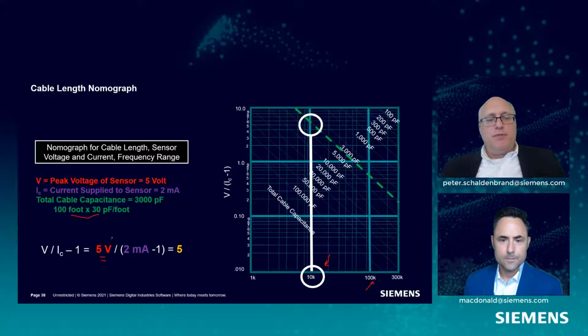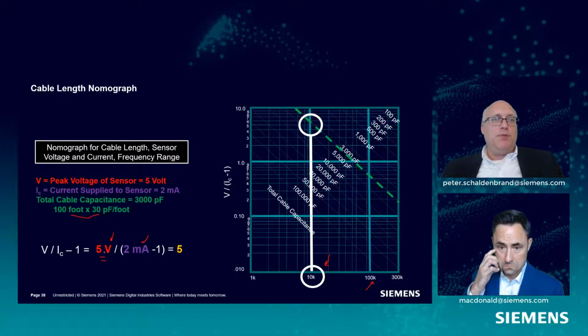It's not a supply for the voltage - that's actually what we're measuring, but that's the current supplied to the transducer. We could say, well, I don't need 5 volts coming back through the wire. I only need to measure up to 1 volt because I use a less sensitive transducer.